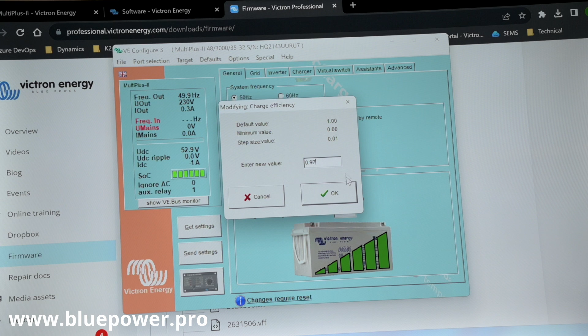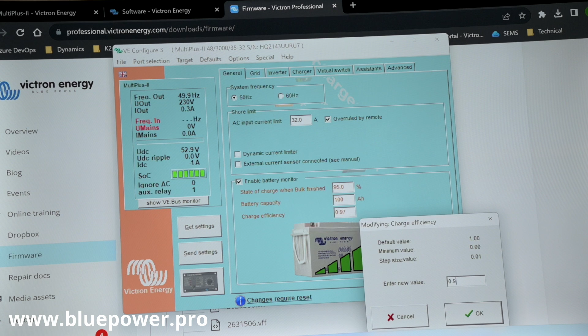But because of the new technology on lithium, we can have efficiencies of up to 99% claimed from the battery charge to discharge cycle. So for the majority of the lithiums, the charge efficiency is going to be 97%. This value works in an increment from 1 being 100 and 0.01 being 1, so just make sure that you put it in as 0.97. If you input the wrong value, it's not going to be able to give you a value without boundaries. So I make sure I type in 0.97 over there. That's good.